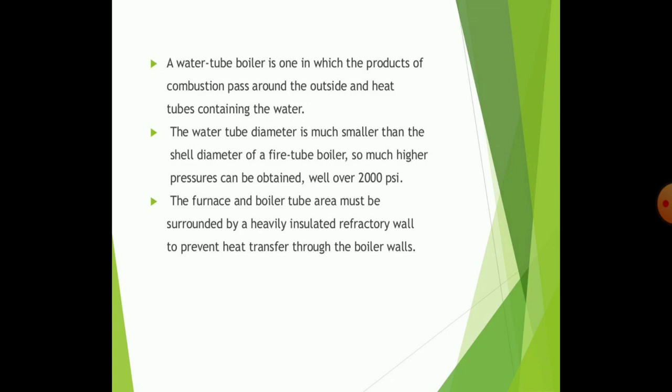The water tube boiler is one in which combustion passes around the outside of heat tubes that contain the water. The water tube diameter is much smaller compared to the shell diameter of a fire tube boiler, so much higher pressure can be obtained — over 2,000 pounds. The furnace and boiler tubes must be surrounded by heavy insulated refractory walls which prevent heat loss through the boiler walls.